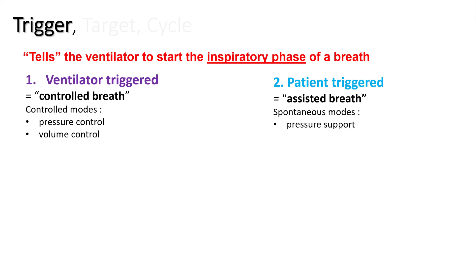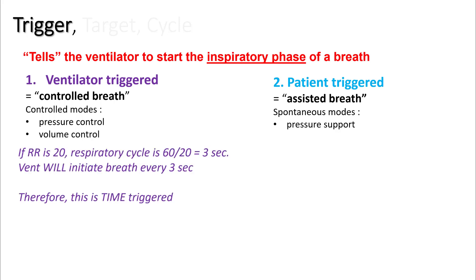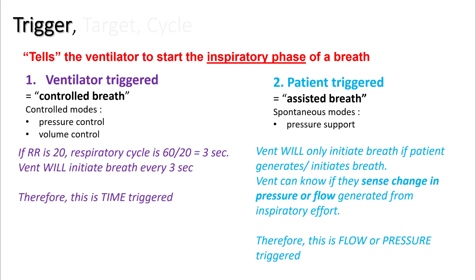Controlled breaths are given in control modes like pressure control and volume control, while spontaneous modes like pressure support are completely patient triggered. For example, if your respiratory rate is set at 20, your respiratory cycle is 3 seconds, so the ventilator will initiate a breath every 3 seconds — this is time triggered. In patient-triggered breath, the ventilator will only initiate a breath if the patient generates or initiates the breath. When someone initiates a breath, they generate negative intrapleural pressure which generates a positive flow, and these two parameters can be sensed by the ventilator. Therefore, patient-triggered breaths are either flow or pressure triggered.